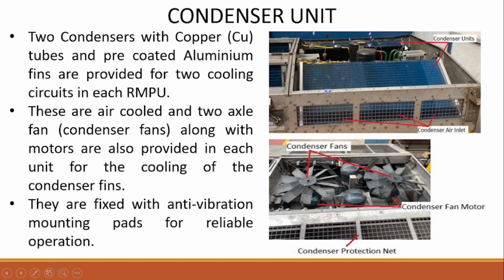Two condensers with copper tubes and pre-coated aluminum fins are provided for the two cooling circuits in each RMPU. These are air-cooled, and two axial fans, along with the motors, are also provided in each unit for the cooling of the condenser fins. In both units, they are fixed with anti-vibration mounting pads for reliable operation.